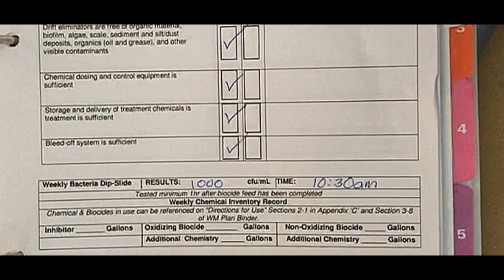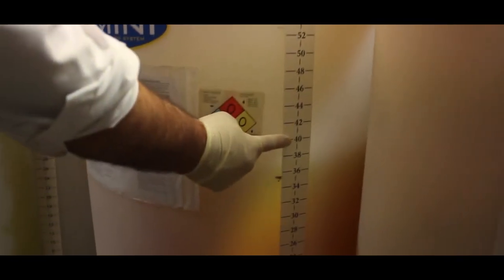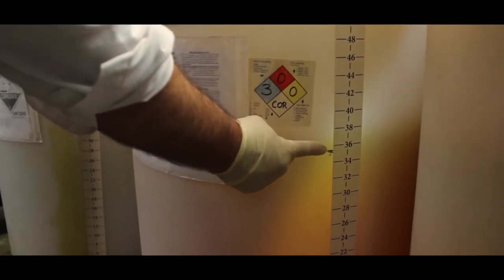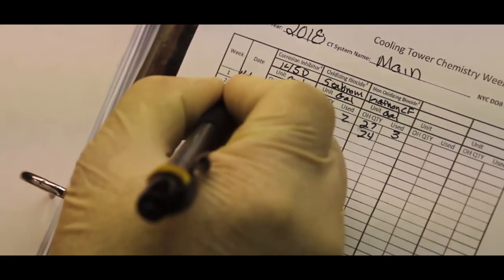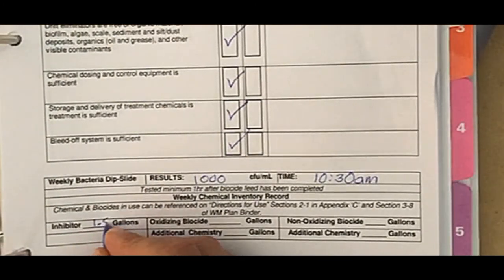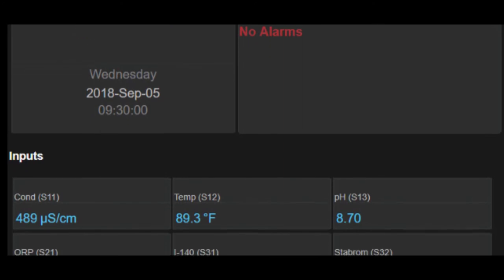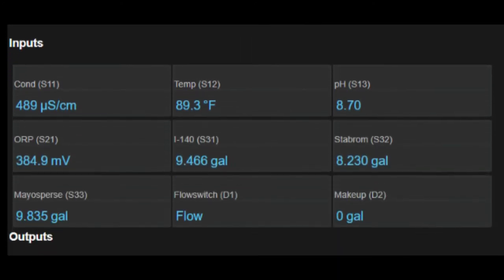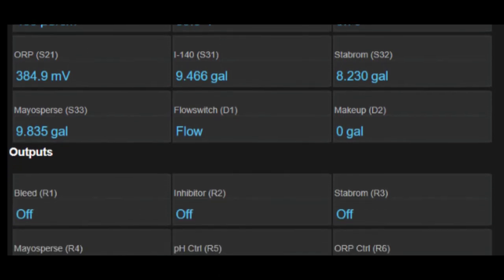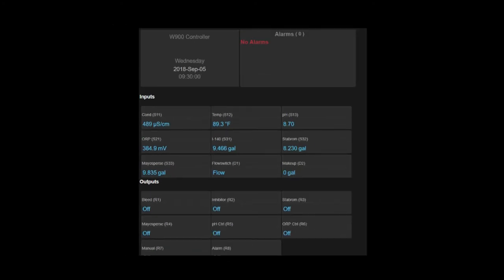There are two methods of gathering inventory. The first is accomplished by shining a flashlight on top of the container and looking on the side of the container to see where the light hits the chemical level. Match the chemical level to the volume number strip on the drum — this is the current week's level. Subtract this week's level from last week's and record the difference as amount used. If you maintain a smart controller with communications, you can receive a daily email from the controller showing chemical levels for all drums. Retrieve the email from seven days ago, compare it to this week's email, subtract the difference, and record it as the amount used. To obtain equipment for these automated emails, contact your water treatment provider.